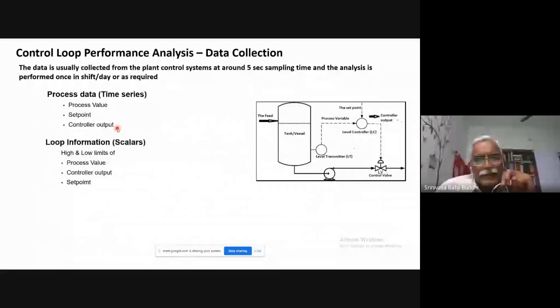Then we also use static information, like typically the high and low limits of the process value, control output, and set point. They are also required for doing this analysis and diagnosis. So we collect this information also. Typically, it is available in the engineering software application that is used in the process plants.